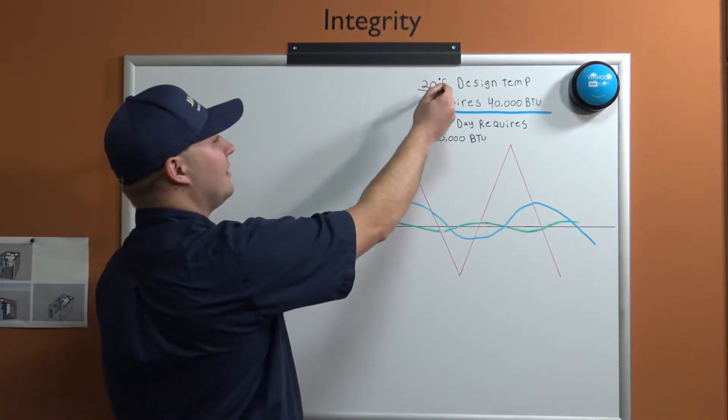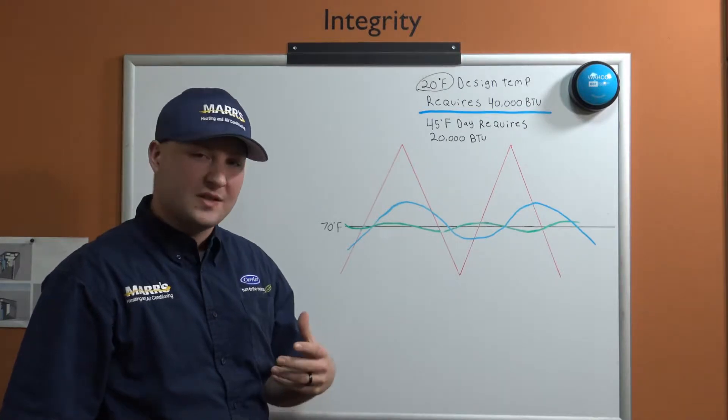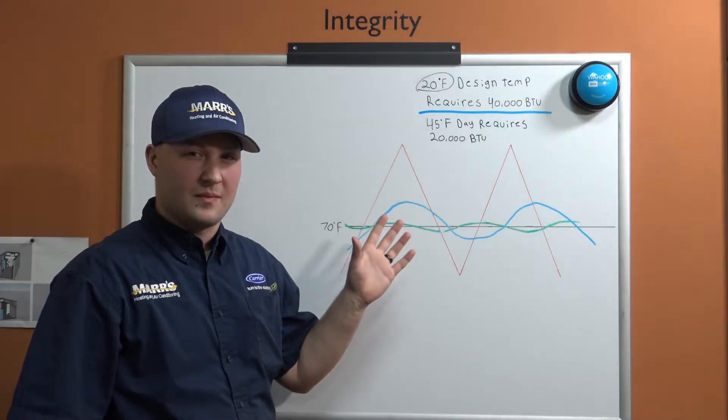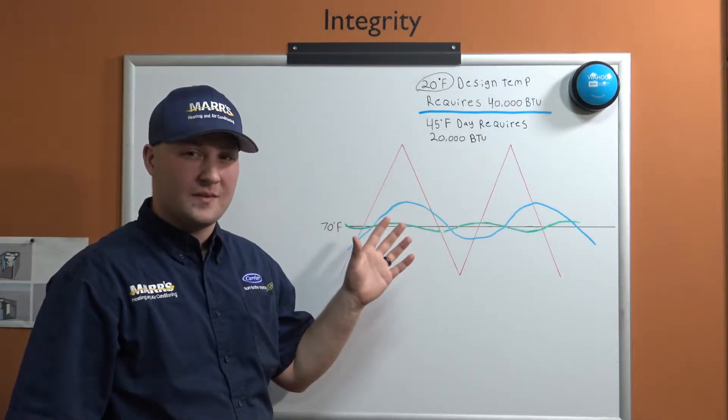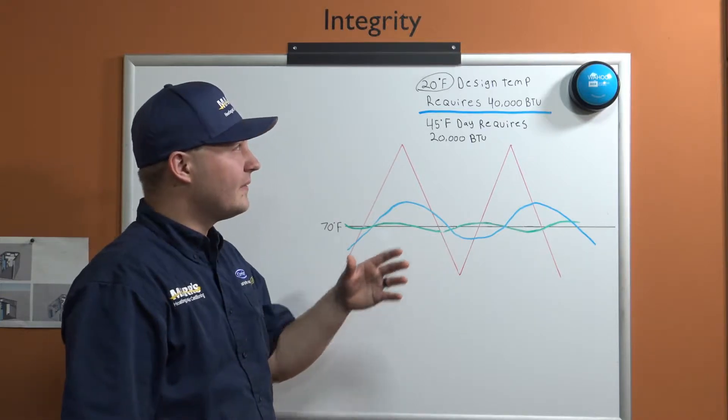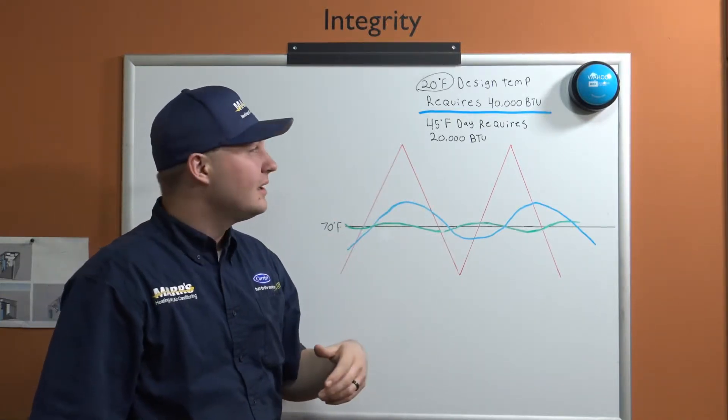This does not mean that we're consistently 20 degrees in this area. This just means this is kind of a worst-case scenario. Actually, this is typically less than five percent of the time that we're going to see 20 degrees, but we still want to size our equipment so that we have that heating capability when it does hit 20 degrees outside.